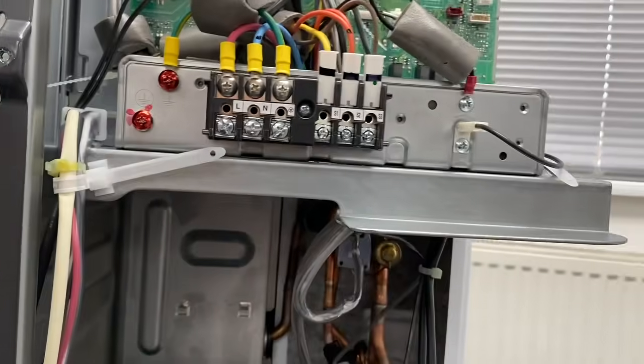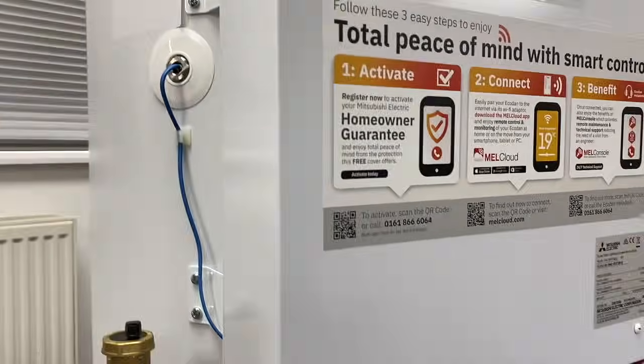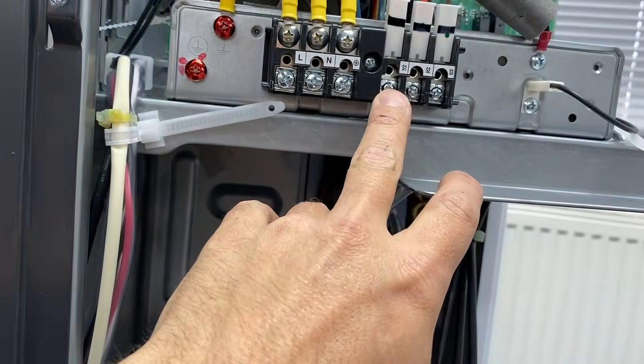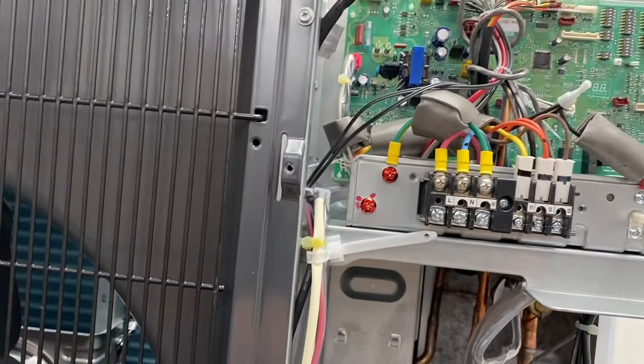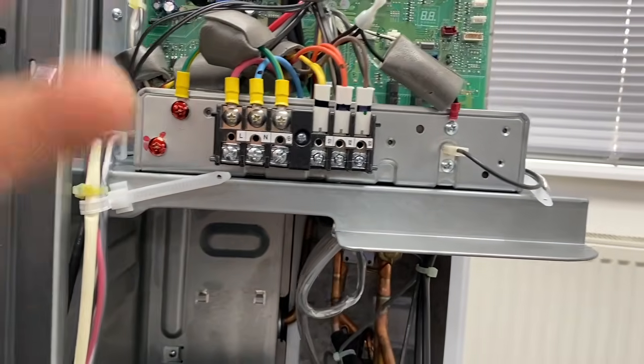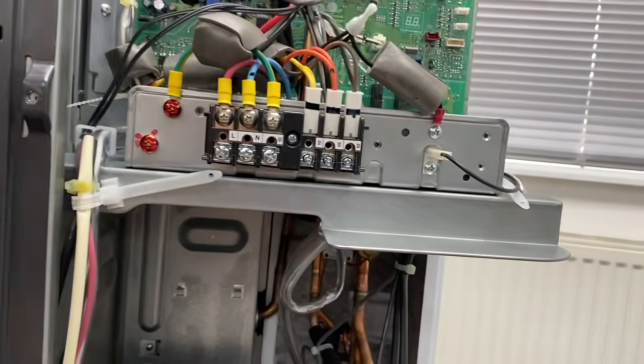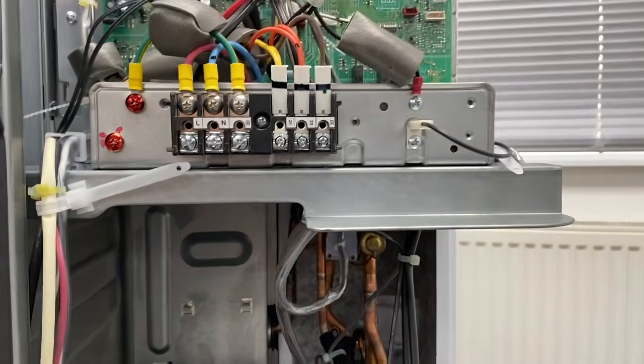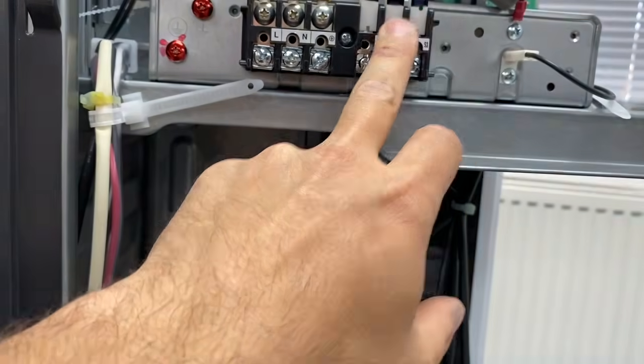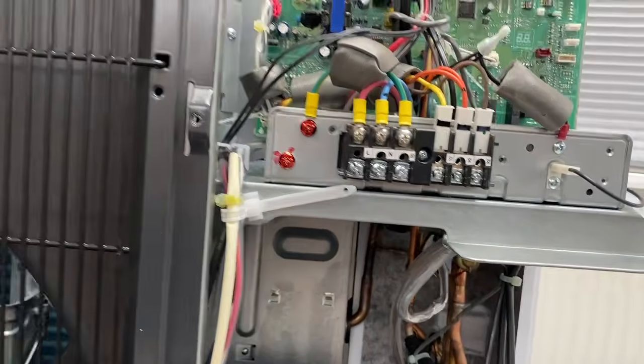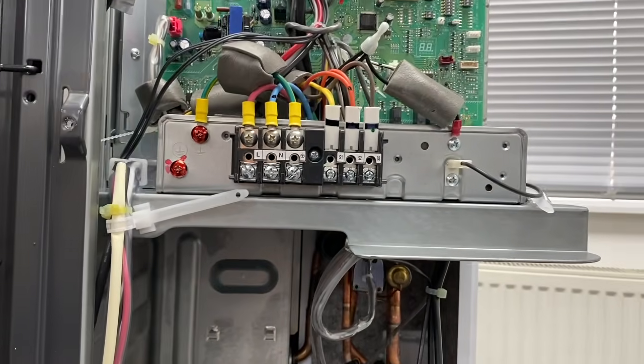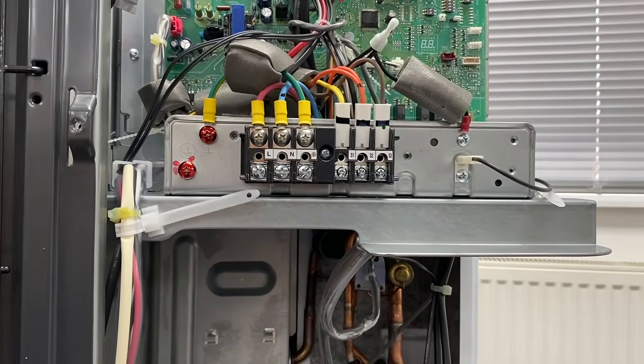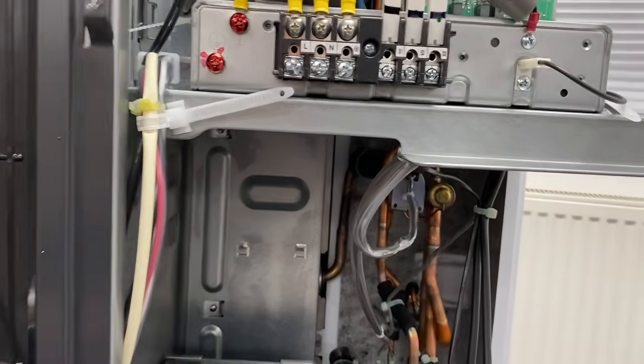Then we've got this. This is S1, S2 and S3. These are basically your signal cables, and they will go inside of the interface in here. So there's very similar computer electronics inside of here. What that will do is take it and give power, then it will give signal, and basically it will talk to each other from whatever distance. We generally put in a 4-core cable, which allows us to go to earth, power and signals, and then the same on the inside of the unit. That's all we really need to be worried about as installers. That's all we should be worried about.